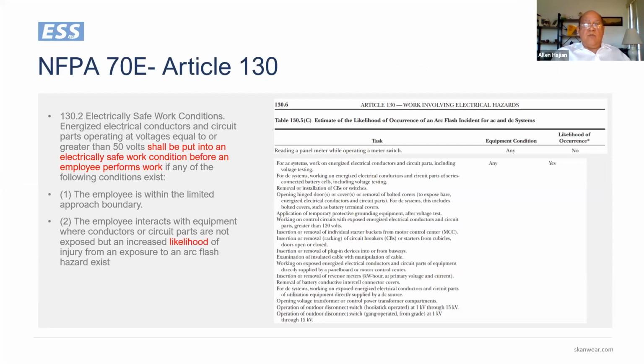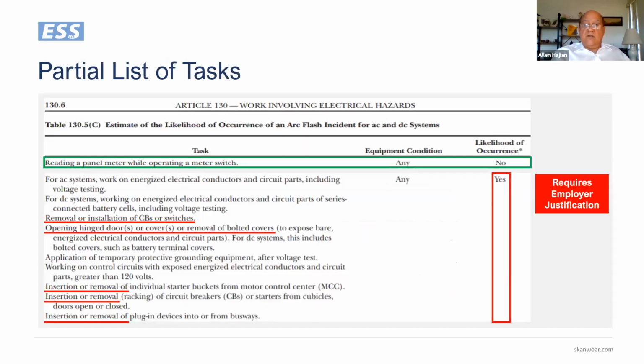That is especially when the employee is within the limited approach boundary or there's a likelihood for increased hazard. As you look at the tables in 130, a lot of employers I've seen say, go to these tables, figure out what you need to wear, and go to work. And that's not the right thing to do. The right thing to do is to identify the work and identify if there is justification for that work. For example, reading a panel meter while operating the meter switch in equipment in any condition, there is no likelihood of an electrical explosion.